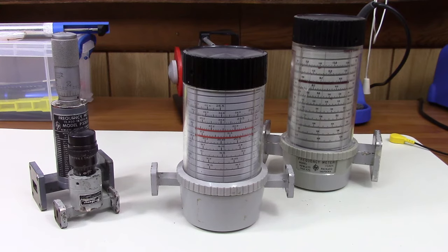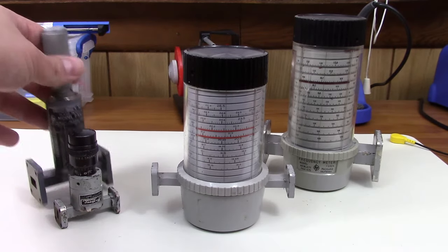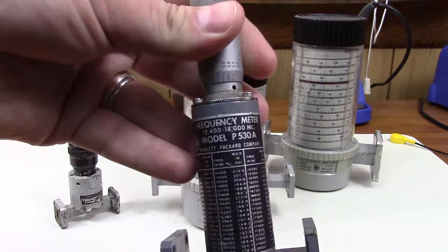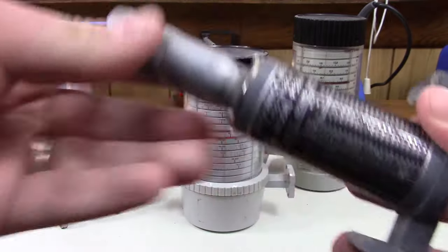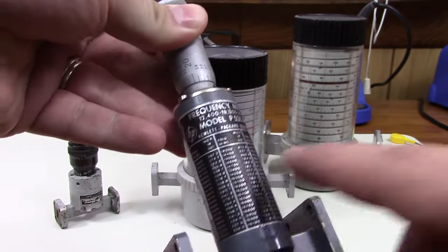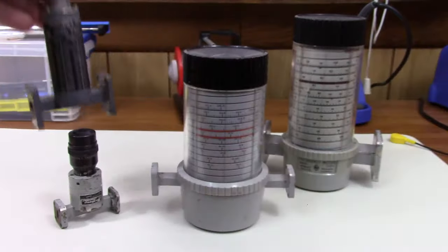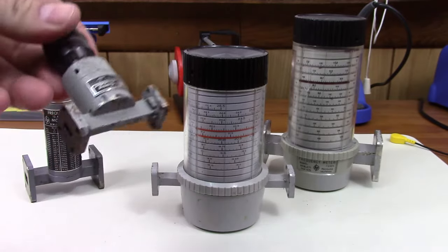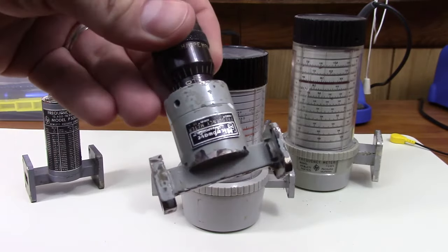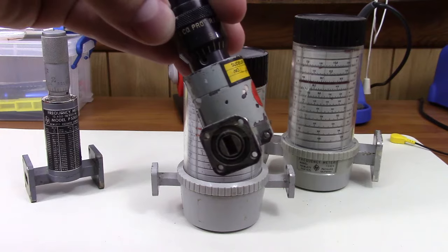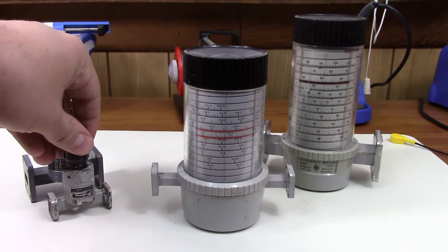There are some slightly different versions. They have the scale up here and on the side they have a little table that you use to translate between this reading and the frequency. Here's a little tiny one from a different manufacturer for the 40 gigahertz range, so you can get pretty high.